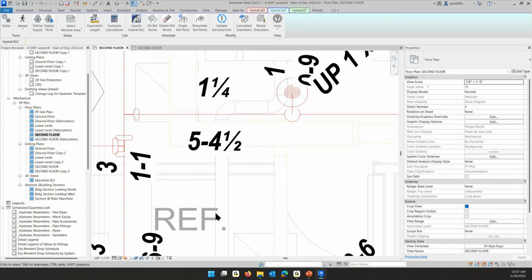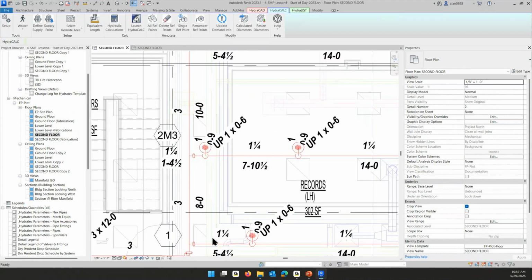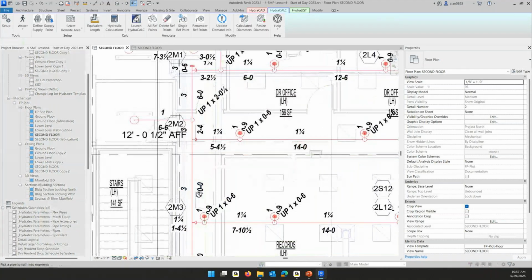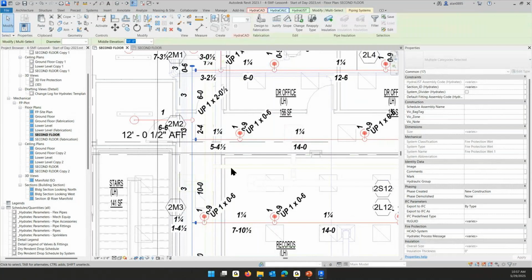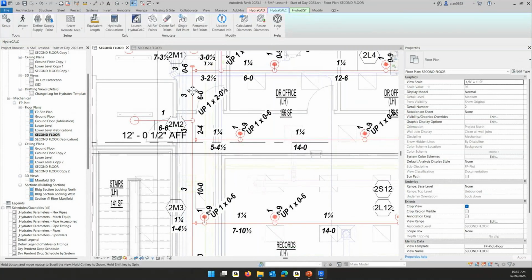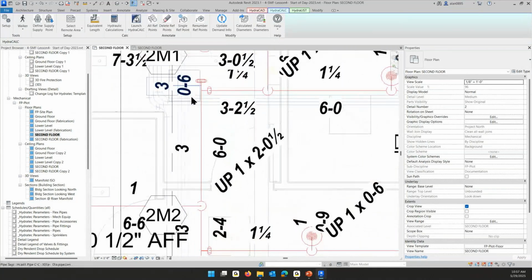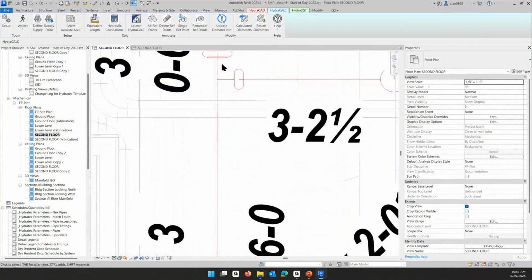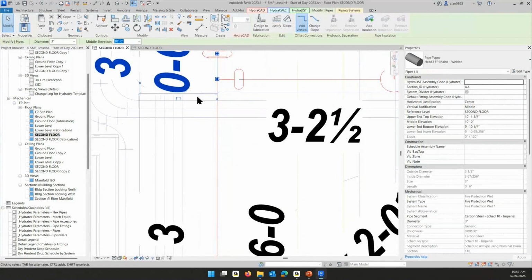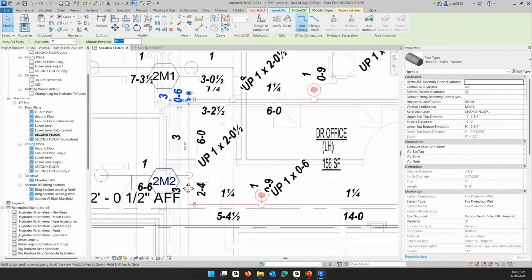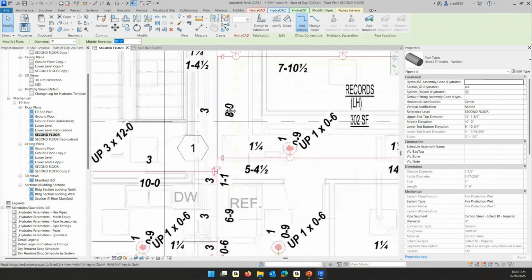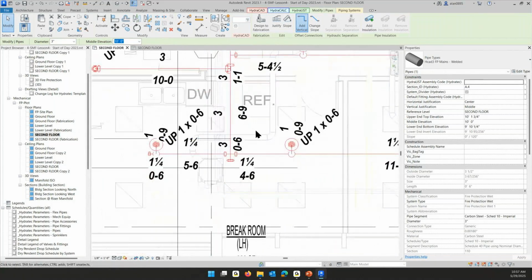And here's my chance, Josh, to say that I used WS to change that from 2.5 to 3, and you used the calculated diameters. They both work, but the calculated diameters isn't my favorite because it forgets about this pipe. Do you see yours is still 2.5 on the end there? I'm looking. Mine's different. Mine changed the end pipe to 3 inch, but it actually kept two of those pipes south, that 6 foot piece and that 10 foot piece. It kept them 2.5.